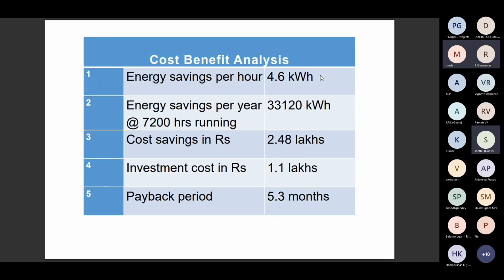So this is the cost economics. Approximately, with 7,200 hours of running in the foundry, 33,120 units can be saved because of this one pump itself. The cost saving is 2.48 lakhs. The investment cost is 1.1 lakhs, and the payback period is only 5.3 months. So the payback was achieved in less than 6 months due to this energy efficient pump. Next.